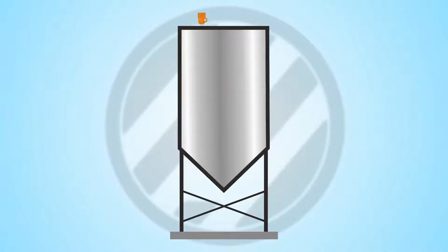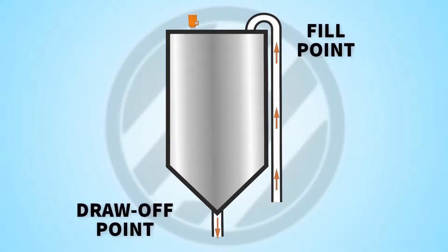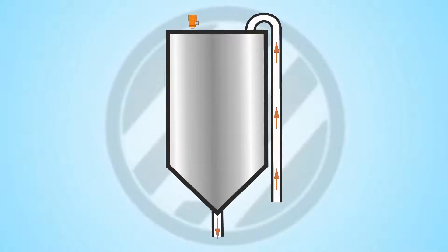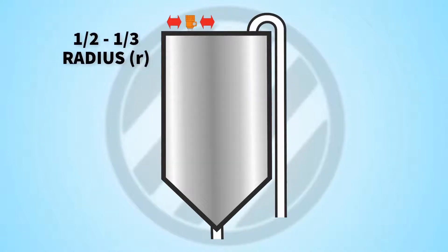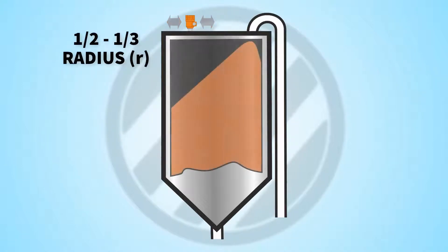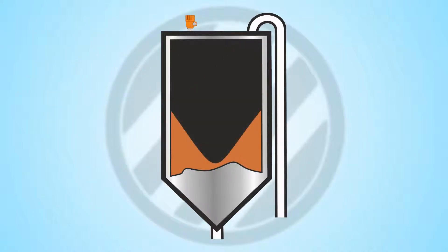Firstly, we need to note key information about the silo. We need to know where it's filled from — this will be via a fill pipe in the top part of the vessel — and where the silo draw-off point is. The radar must be mounted away from the fill pipe to avoid false readings. The recommended positioning is about half radius to one third radius, which gives a good average of the level during filling and emptying, both of which will have a conical shape.